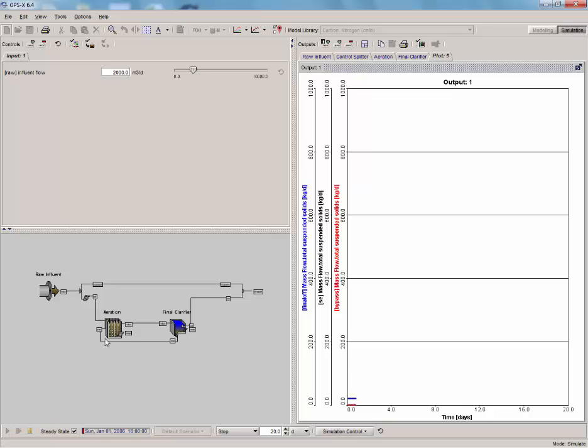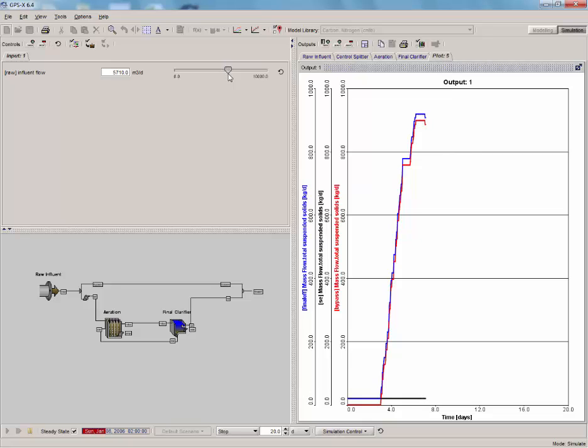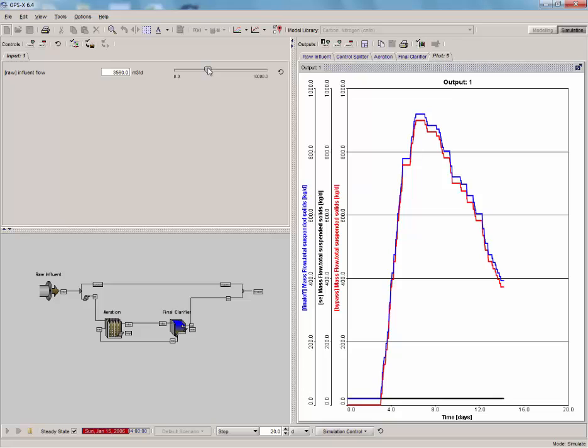Try varying the influent flow during the run. Notice that when the influent flow rate is about 2000 m³ per day, which is the pump flow rate for the control splitter object, some flow will begin to bypass the plant showing up in the bypass stream. Adjust these values and try to reduce the total mass flow of the solids discharged into the receiving water.